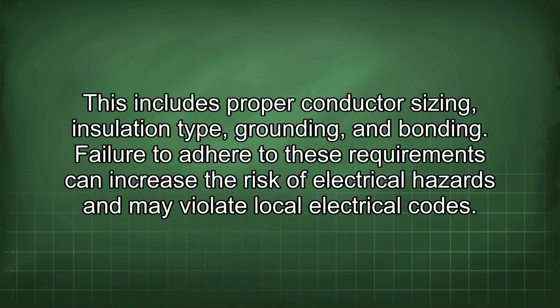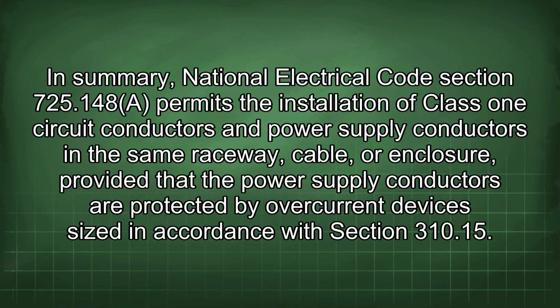This includes proper conductor sizing, insulation type, grounding, and bonding. Failure to adhere to these requirements can increase the risk of electrical hazards and may violate local electrical codes. In summary, National Electrical Code Section 725.148 permits the installation of Class 1 circuit conductors and power supply conductors in the same raceway, cable, or enclosure, provided that the power supply conductors are protected by overcurrent devices sized in accordance with Section 310.15.